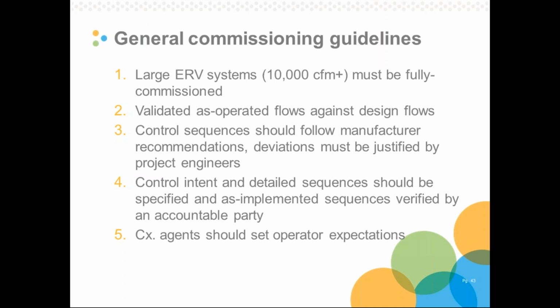We've got to validate as-operated flows against design flows. They're different, they're going to change, and we have to know what they are if we want to understand our energy savings. Control sequences should follow manufacturer recommendations, and deviations should be justified by project engineers. The manufacturers really know what they're doing. You can tell from their product literature, the manufacturers I talk to, they've got a handle on how their system should be working, and if we're going to deviate from that, it has to be a justification that everybody can later reference.